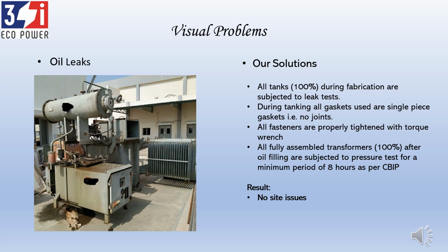We subject the fully assembled transformer to a pressure test, each one for a minimum of 8 hours as per relevant standards like CBIP or IS 1180, whichever standard applies. This is a routine test for us - even if the customer doesn't specify it, we do it for all transformers. Only once these are successfully done is the transformer eligible for dispatch, with all other conditions satisfied.